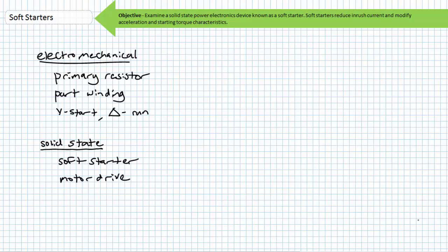Recall that the electromechanical means are all characterized by a clear and definite transition from start to run mode. For a primary resistor reduced voltage starter, either the primary resistors are in or not in the circuit. For a part winding reduced voltage starter, either part of the windings are connected to full voltage or all of them. For a Y-start delta run reduced voltage starter, either the motor is in Y configuration or delta configuration. There is no in-between stage, and the starter never makes a smooth, gradual transition from start to run.